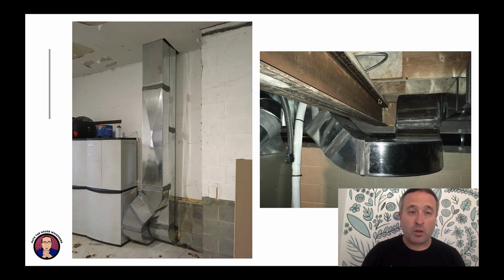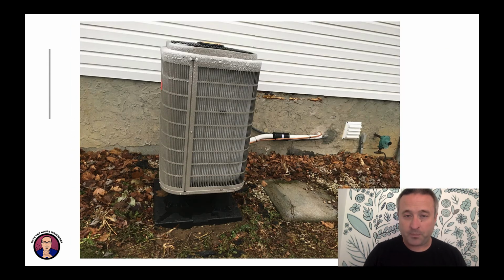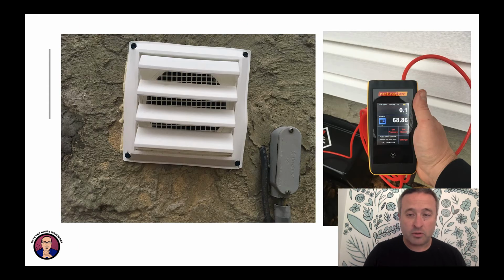And important note, I offered a duct design here, and he did not take it. So the second floor probably could have stood more ductwork than what it got. But, you know, if you don't specify it, you get whatever the contractor wants to do. So it worked okay, but it would have been better if this ductwork was a bit bigger. Here's the outdoor unit right before defrost.